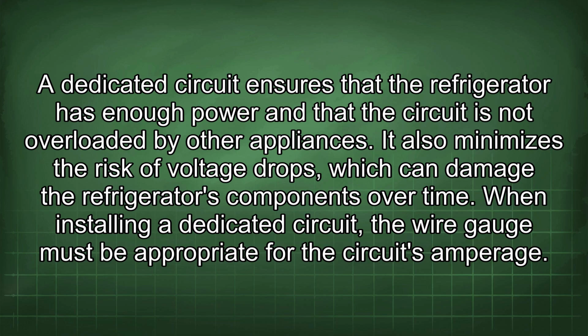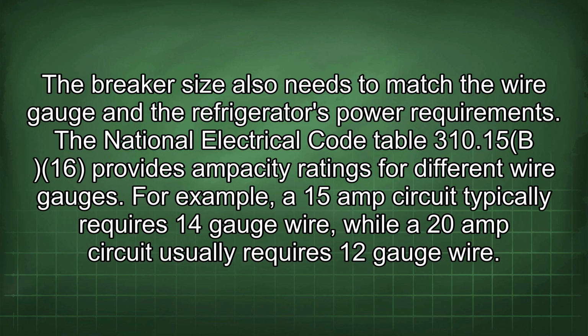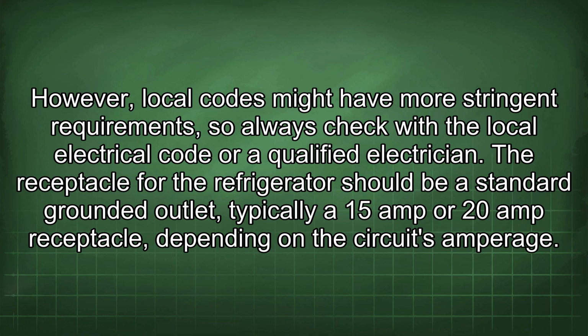When installing a dedicated circuit, the wire gauge must be appropriate for the circuit's amperage. The breaker size also needs to match the wire gauge and the refrigerator's power requirements. The National Electrical Code Table 310.15(B)(16) provides ampacity ratings for different wire gauges. For example, a 15-amp circuit typically requires 14-gauge wire, while a 20-amp circuit usually requires 12-gauge wire. However, local codes might have more stringent requirements, so always check with the local electrical code or a qualified electrician.